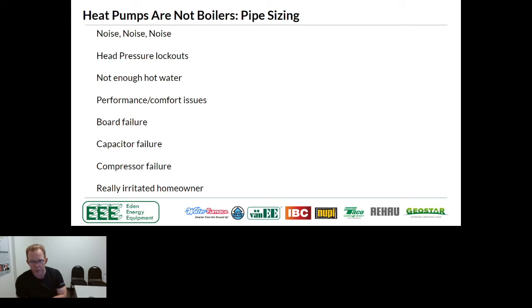Well, you're going to go out there, and depending on the technology on the equipment, you'll see a whole row of high head pressure lockouts. If you don't fix it, I'm sure Trevor Matthews has already told you guys what's going to happen if you don't fix that. Spoiler alert, you're going to need a new compressor. Not a good idea. The most common thing you'll get the complaint about is it's noisy and I never have enough hot water. So again, that's an example where you put a traditional indirect on a hydronic heat pump, or better yet, there isn't even an indirect. You just got 60 closely spaced T's on a unit that can't produce enough higher temperature water for the last set of closely spaced T's, and we just move a few T's in the design.